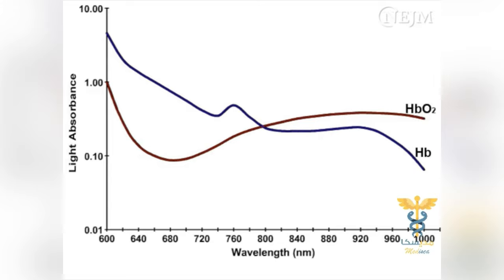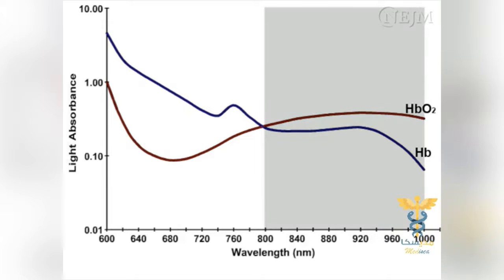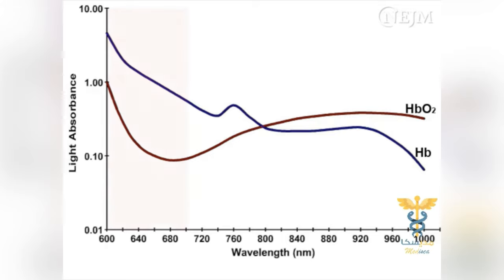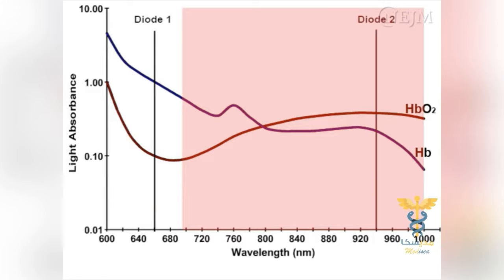Pulse oximeters function on the principle that oxygenated and deoxygenated hemoglobin absorb red and infrared light differently. The light absorption of deoxyhemoglobin is greater at wavelengths of 600 to 800 nanometers, while the light absorption of oxyhemoglobin is greater at wavelengths of 800 to 1,000 nanometers. One light-emitting diode emits light in the red spectrum at a wavelength of 660 nanometers, at which the light absorption of deoxyhemoglobin is greater than that of oxyhemoglobin. The other diode emits light in the infrared spectrum at a wavelength of 940 nanometers, at which oxyhemoglobin absorbs more light than deoxyhemoglobin. The microprocessor analyzes the light absorption of the tissues at each wavelength to determine the respective concentrations of oxyhemoglobin and deoxyhemoglobin.